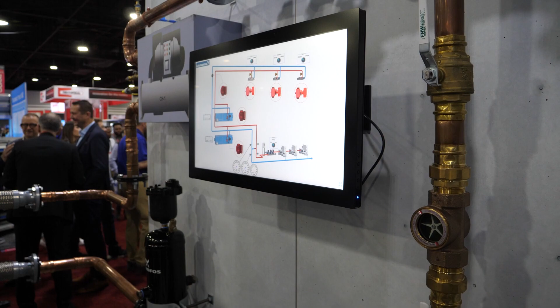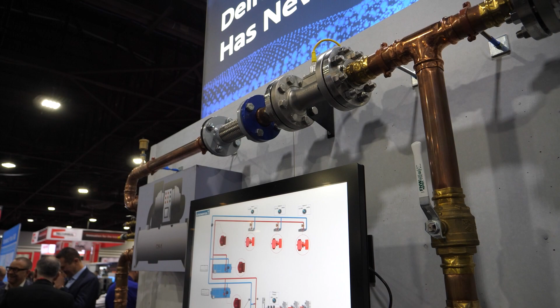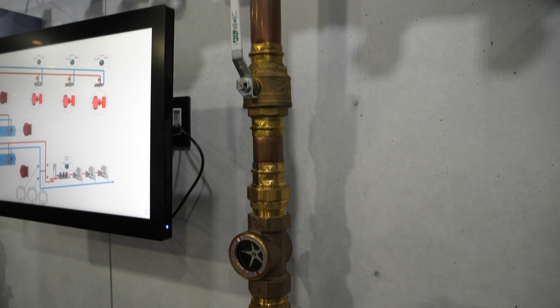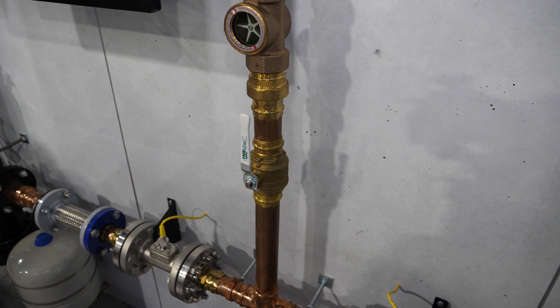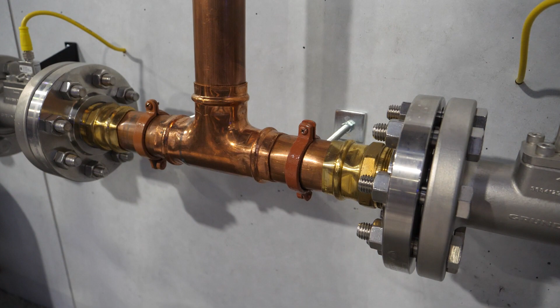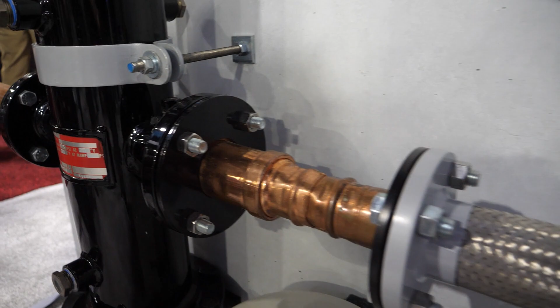The industry has gone the route of variable primary, and there are benefits to that, but it makes control difficult. So we want to utilize the same piping scheme you'd normally have, with our bypass here. The significant difference with our system versus others is it's not a controlled bypass. We're not putting a control device there to manage the flow through it. Our goal is to eliminate the flow through it entirely, which ensures our secondary and primary are hydraulically balanced. That's surprising, because most of the industry nowadays is trying to connect things, so it's interesting you're taking the opposite approach.